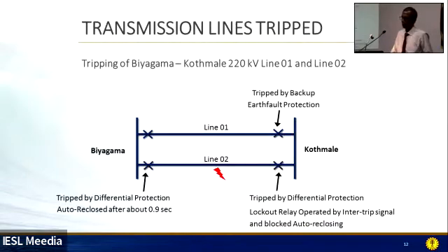But after that, because of this permanent neutral unbalanced current in this transmission network, the earth fault relay could not reset. Because of that, after about 22 seconds, the relay operated and tripped that line as well.